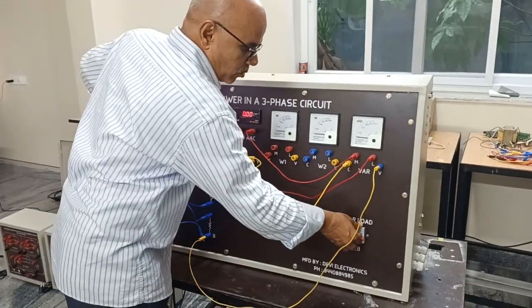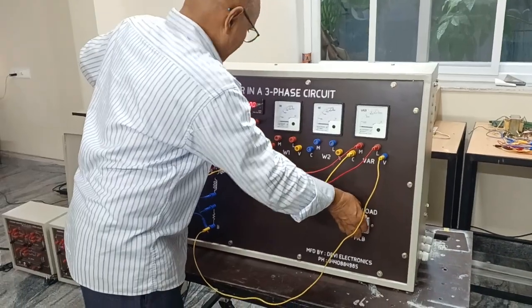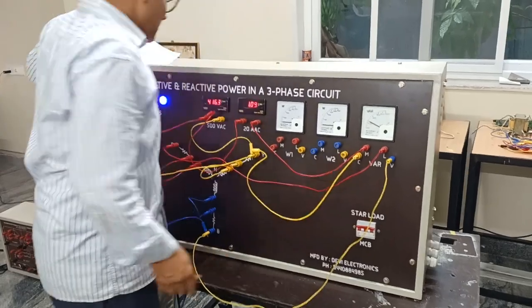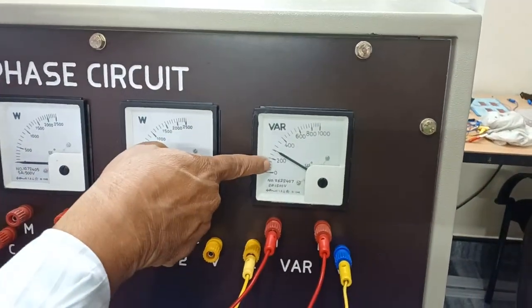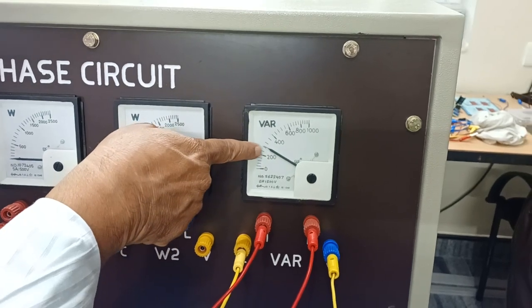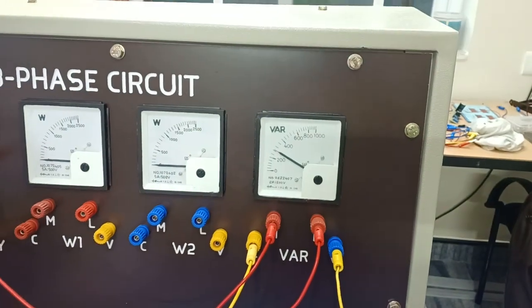Now I have applied the load. It is a single step. At 415 volts, current is 1.09 amps, and the wattmeter reading is around 325 to 350 watts.